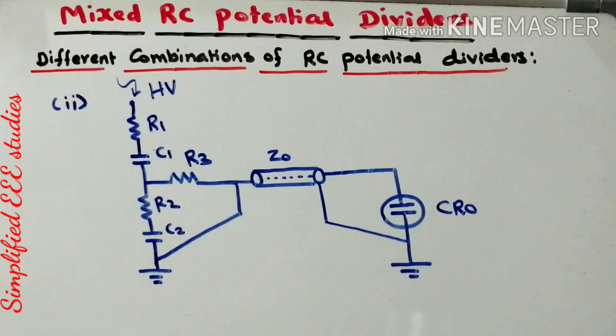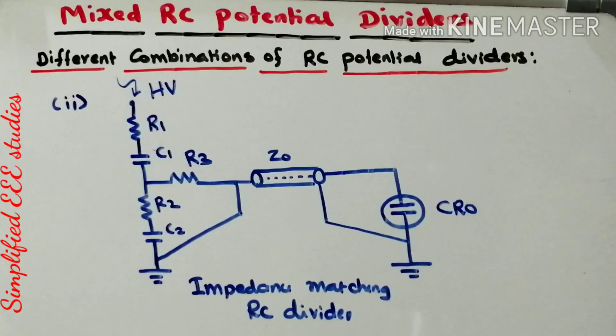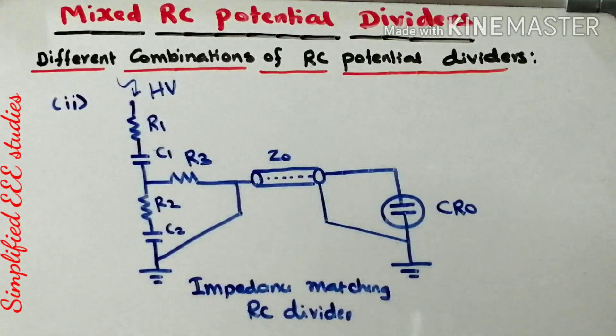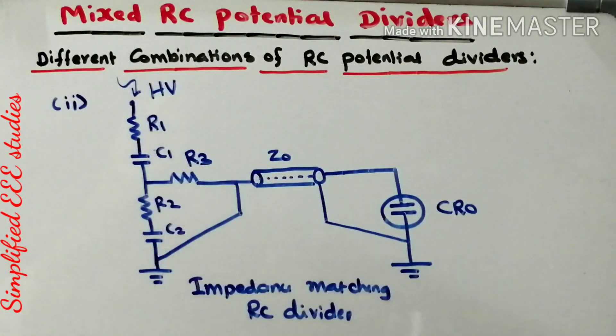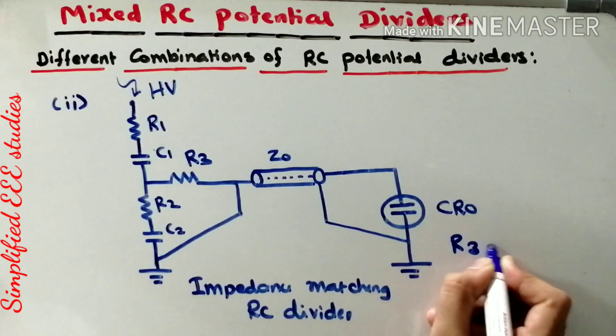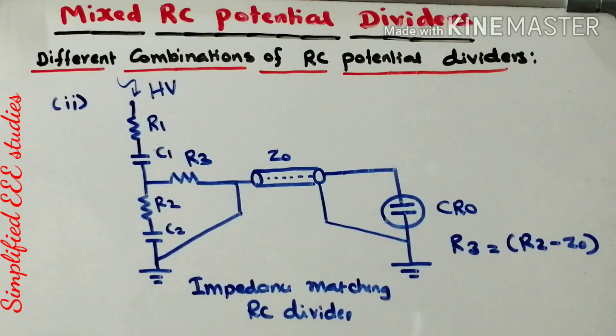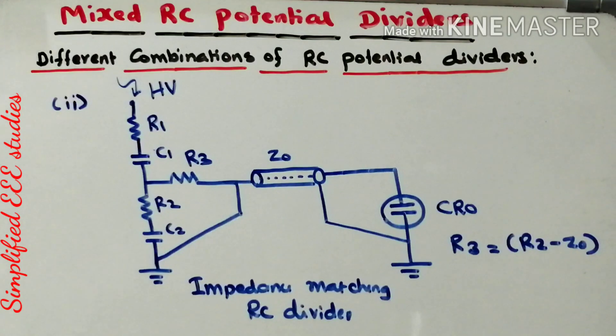The second combination is known as the Impedance Matching RC Divider. The total high voltage is measured using the low voltage arm and high voltage arm. The low voltage arm is directly connected through a coaxial cable to the CRO. The value of R3 is calculated by the formula: R3 equals R2 minus Z0, where Z0 is the characteristic impedance. This type is also helpful for calibration purposes.